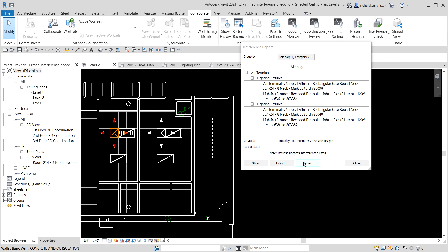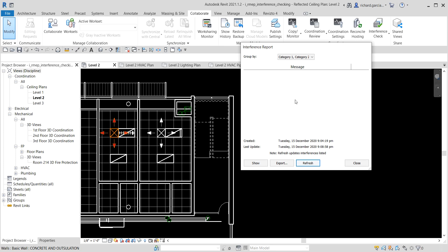Once you've fixed the clash, click Refresh in the interference report dialog. After refreshing, you can see there are no more clashes. That's what you do: fix the clash and then refresh the interference report. This minimizes coordination work when you later use Navisworks.